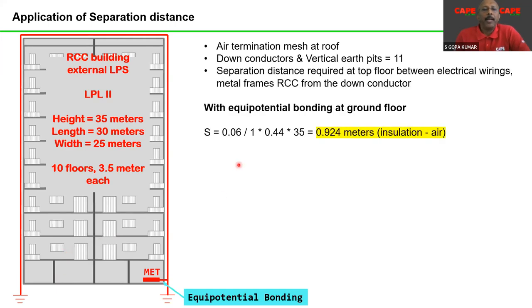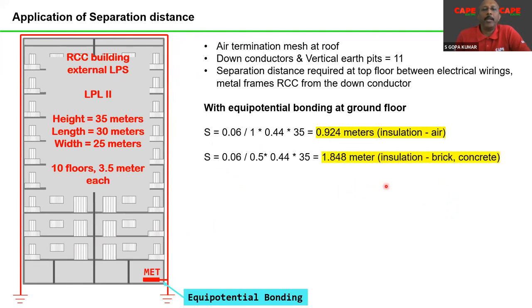So, if we take the values from the constants, S equals Ki divided by Km, into Kc, into L. L is nothing but the distance from the top of the building down to the equipotential bonding, the height of the building in this particular case. If we calculate, the separation distance required in this kind of building, a 10-floor building, is about 0.924 meters. Almost 1 meter of insulation is required in air, almost 2 meters of insulation is required in case of brick or concrete.